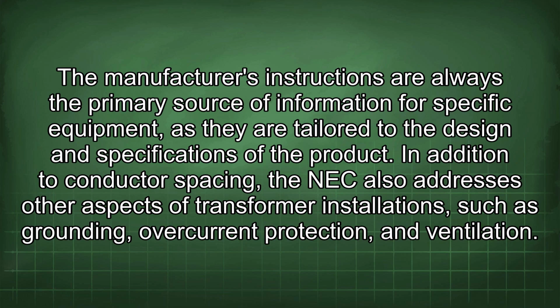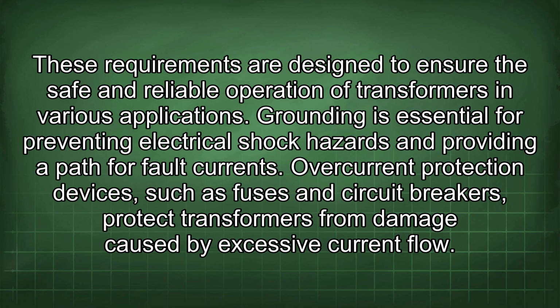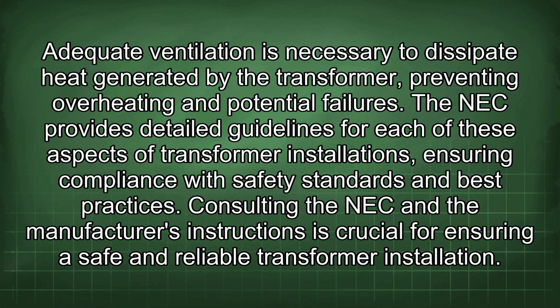In addition to conductor spacing, the NEC also addresses other aspects of transformer installations, such as grounding, overcurrent protection, and ventilation. These requirements are designed to ensure the safe and reliable operation of transformers in various applications. Grounding is essential for preventing electrical shock hazards and providing a path for fault currents. Overcurrent protection devices, such as fuses and circuit breakers, protect transformers from damage caused by excessive current flow. Adequate ventilation is necessary to dissipate heat generated by the transformer, preventing overheating and potential failures. The NEC provides detailed guidelines for each of these aspects of transformer installations, ensuring compliance with safety standards and best practices. Consulting the NEC and the manufacturer's instructions is crucial for ensuring a safe and reliable transformer installation.